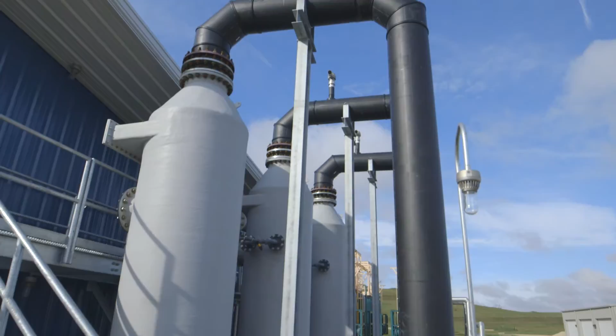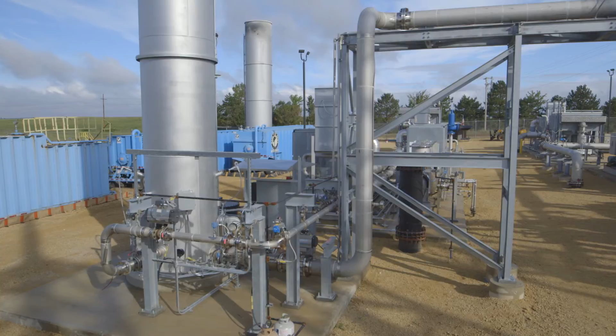This system is important to us because it pulls H2S out of the gas stream. H2S is a big concern for us because, as everybody knows, it is poisonous. On top of being poisonous, it's very corrosive. So you can understand a corrosive gas being combusted in the engines could certainly be detrimental to the equipment. For that purpose, we pull that H2S out. We do that through 3 scrubber towers in conjunction with a chemical reagent slurry that is mixed into those scrubber towers with the gas.